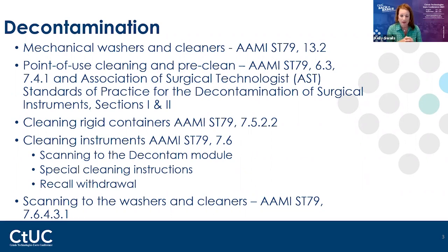So I had a staff member who had swapped out, at the same time, the detergent and the instrument lubrication, and mixed up the bottles or the hoses. And so we went a couple days without knowing that that had happened until we ran that wash test and it didn't pass. Just trying to figure out why it didn't pass, and then figured out the problem. So right then and there, all those instruments that were washed in between that change of the chemicals until that next wash test, none of those were properly cleaned.